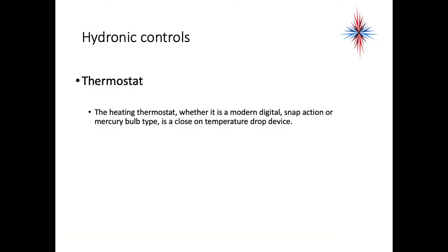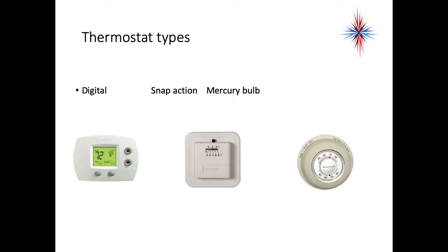The core control of the entire system — what starts it and stops it — is the heating thermostat. It could be digital, snap action, or a mercury bulb. It's a close-on-temperature-drop device, meaning the switch inside closes the circuit as the temperature drops below the set point. You're not seeing many mercury bulbs anymore, so if you pop the top on one, don't be surprised if you see electronics inside.